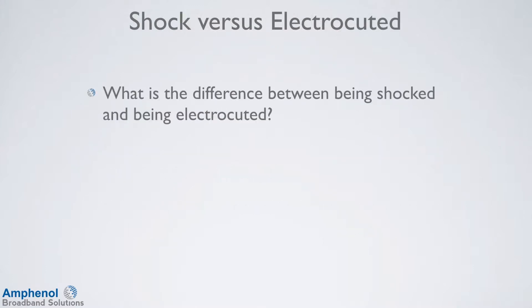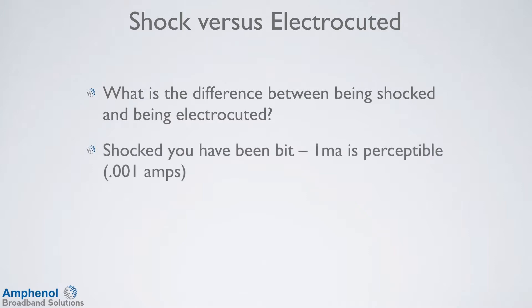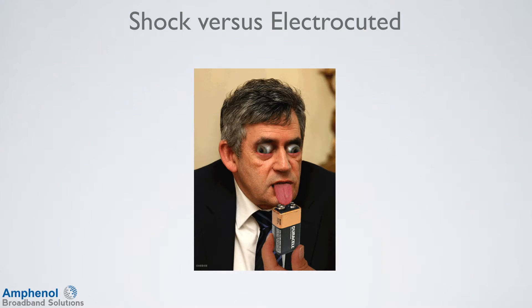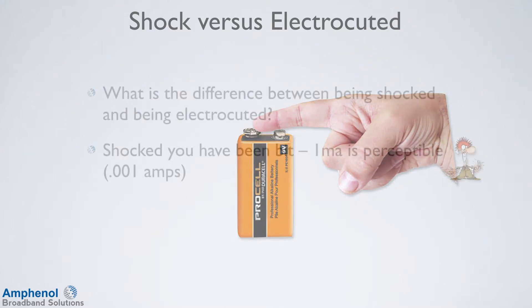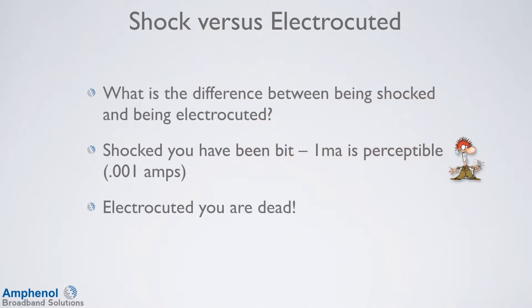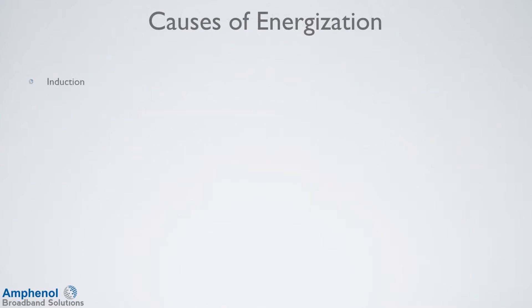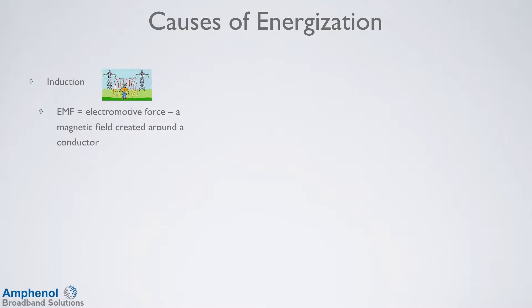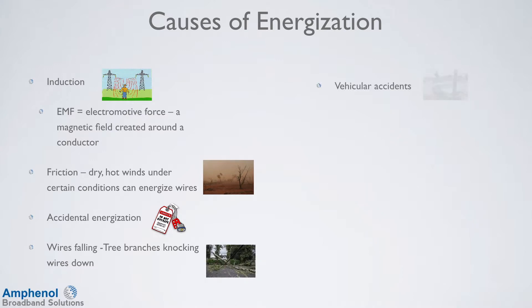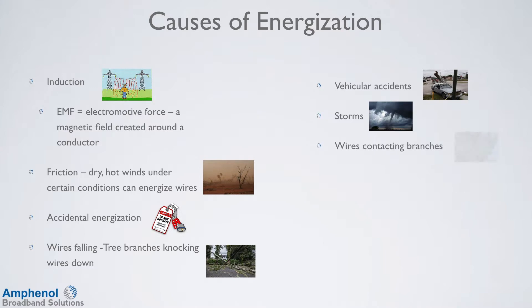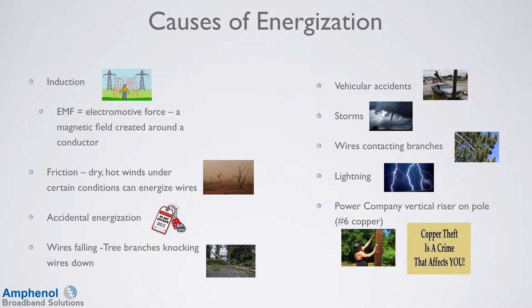Let's look at the difference between being shocked and being electrocuted. Shocked means you have been bit — one milliamp is perceptible, which is only one thousandth of an amp. How do you check 9-volt batteries? Using your tongue, which is very sensitive — putting a finger across does nothing, as the outer two layers of skin have no nerve endings. Electrocuted means you're dead. There are many things that can cause conductors to become energized: induction from close proximity to something, especially if parallel; you should maintain 12 inches from power secondaries when parallel in a home or on a pole. Also friction, accidental energization, down wires, car-pole accidents, storms, power lines contacting branches, lightning, and missing power company vertical risers on a pole.